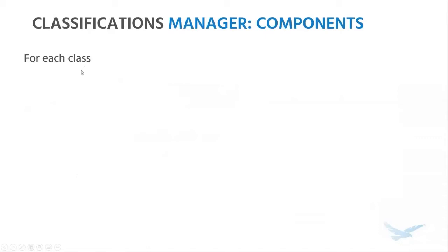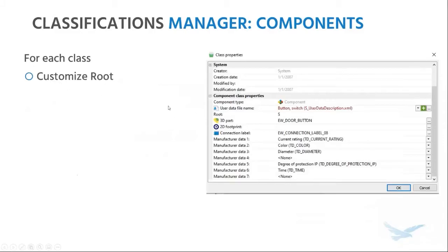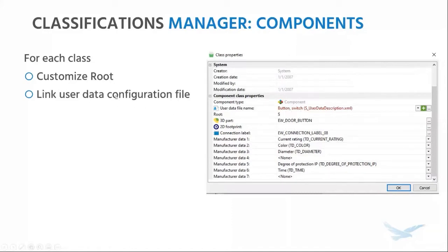You can take it further with classes — for each class, you can set up properties that propagate to all items in that class, including part numbers. In the properties of the class, you can identify a default root. So if you've noticed that all circuit breakers default to Q as a root, or all motors start with M, that's where this information comes from. You can also link a specific user data configuration file to each class. There are about 20 available user data fields that are typically renamed to reflect custom properties, and this renaming information is retained in the user data configuration file. By linking a class to a unique configuration file, you're essentially setting up each class to have its own set of custom properties.